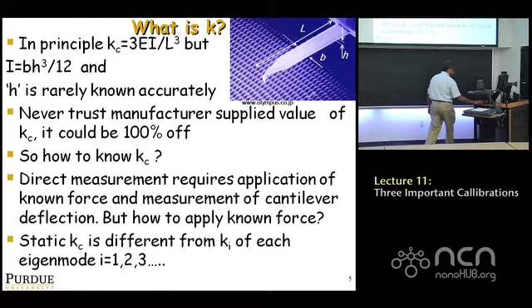So if you do static, you'll get a different value. If you do dynamic in the first mode, you'll get a different value of spring constant. The second mode will be a different value. So really, there are many different spring constants associated with the cantilever. We refer to K sub C as the spring constant when you apply a simple point force and it statically bends. We call it the static spring constant of the cantilever. Then we have K1, K2, K3, representing the spring constants of the first eigenmode, the second eigenmode, third eigenmode, and so on. Okay? The question is, how do we figure all this out?